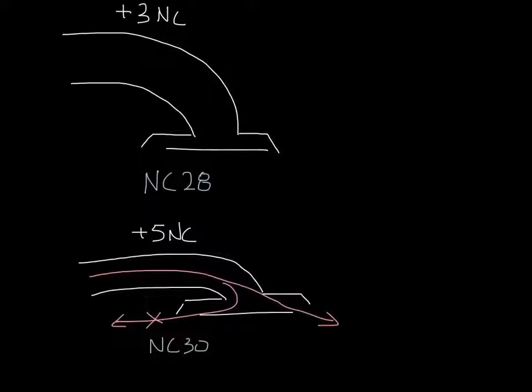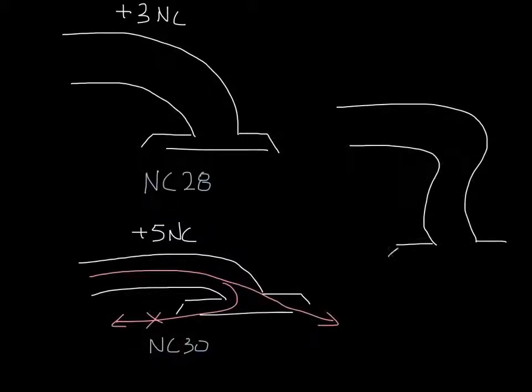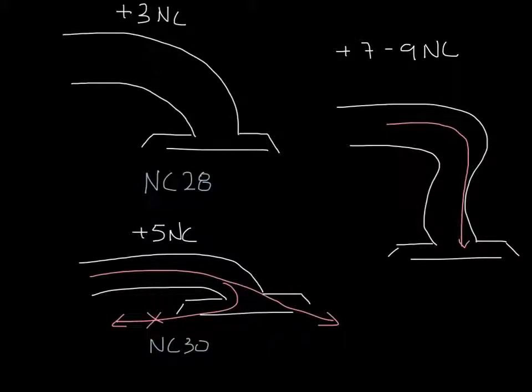The worst case is when the flex duct is kinked. This is pretty common too. Even a small bend like this is going to force the air to one side of the ductwork and possibly out one side of the diffuser. This can add 7 to 9 NC to catalog data. So our diffuser that was cataloged at NC25 would sound more like NC32 or 34 installed like this.